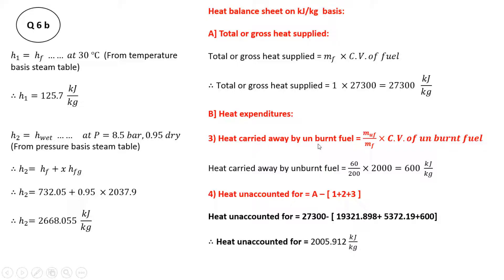The next part is heat carried away by the unburned fuel. Since the heat balance sheet is on a per kg basis, we divide mass of unburned fuel by mass of fuel: 60 divided by 200, multiplied by calorific value of unburned fuel 2000, giving 600 kJ per kg. The last part is heat unaccounted for, which equals total heat supplied minus the first, second, and third parts already calculated: 27300 minus 19321.898 minus 5372.19 minus 600, giving unaccounted heat of 2005.912 kJ per kg.